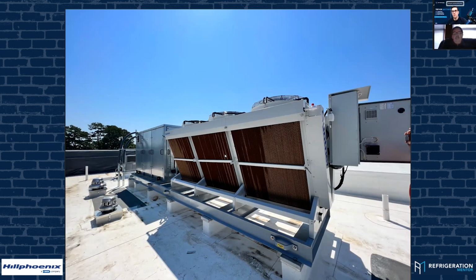Okay. And all right. Why this is important is now we're reducing the amount of flash gas going into that receiver. So we're keeping it below the critical point. And you'll actually see the condenser discharge pressure run anywhere between 1050 and 1150 at 95 degree ambient versus 1300. And a lot of our customers like Wegmans and such are actually starting to put these adiabatic on their standard HFC systems. Yeah. But why not? Well, it works, and it all depends on where it's at. You know what I mean? Some places they're going to be more effective and more efficient than other places, depending if it's super humid all the time, or it's not. It's a really cold place and it's always cold, and you just stay in subcritical.